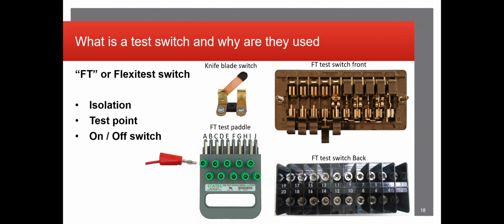We also, as I said before, have safety purposes for some of these test switches. As you can see on the bottom right of the test switch front, there are little tabs at the base. Those are primarily used for current circuits. I'm sure you guys haven't seen it firsthand, but opening a current circuit that is live is extremely dangerous and very bad for the current transformer itself. You never want an open CT. It causes damage to the current transformer. It will cause a misoperation on everything that surrounds that current transformer, and it could lead to disaster on this end in the control house at the test switch front.